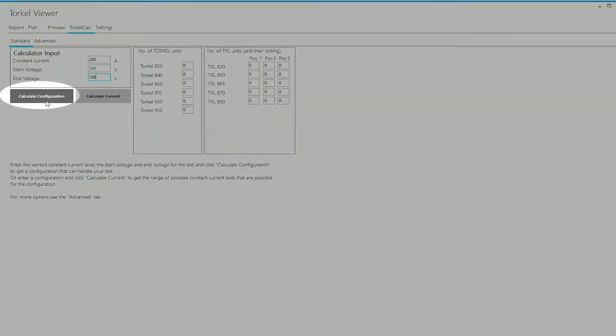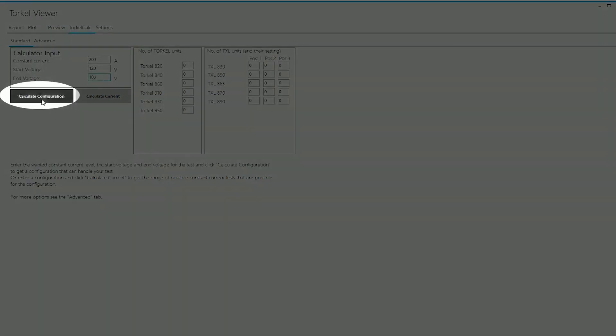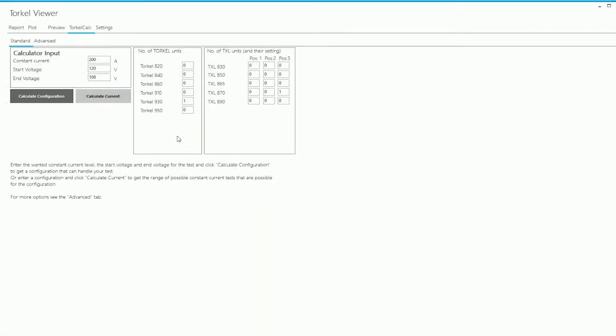When I click on Calculate Configuration, the program tells me that this test can be run using a Torkel 930 and a TXL 870 and the switch on the TXL 870 would need to be on position 3.